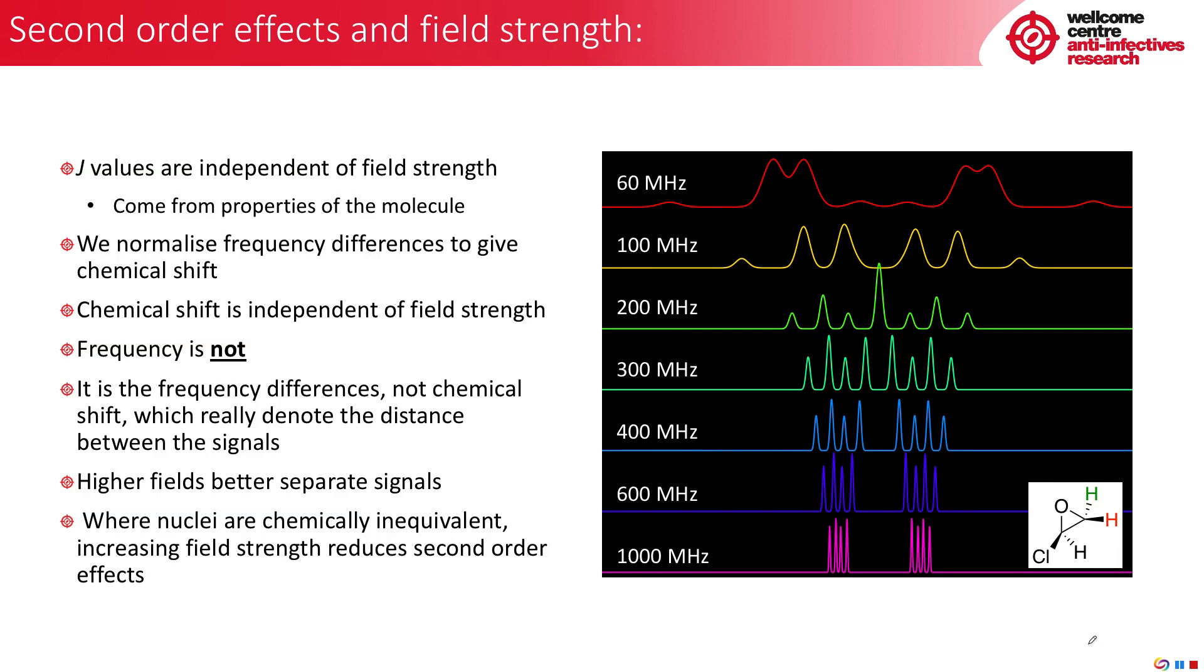Now, you're used to seeing spectra in a format where chemical shift is displayed and it is also independent of field strength. However, chemical shift is a useful normalization tool we employ where we essentially normalize out the difference in frequency. What your NMR spectra actually measures for the nuclei is a frequency and the frequency is not independent of the magnetic field. And it is the frequency differences, not the chemical shift differences, which actually denote the difference between the signals. And the way this shows up in your spectra is that you will see the standard chemical shift. But if you were to actually look, the frequency range contained within one to two ppm is different from a 400 megahertz spectrometer to a 100 megahertz spectrometer. So it would be four times greater.